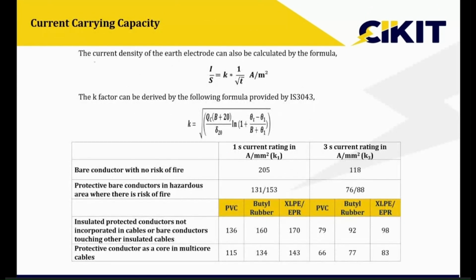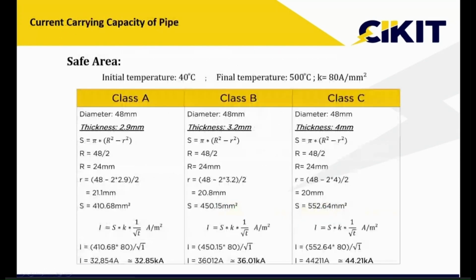And the most important thing is the current carrying capacity. Based on this current carrying capacity only, we decide the size of the conductor. The standard has provided the formula for calculating this cross-section current carrying capacity also. Here you can observe that I by S is equal to K into 1 by root T. So if I solve for I, it will be S K by root T. From this, we can calculate the cross-section area of the particular conductor.